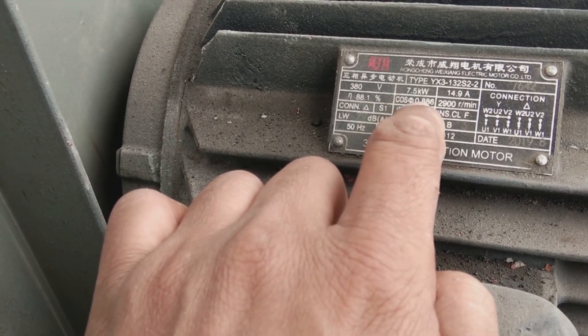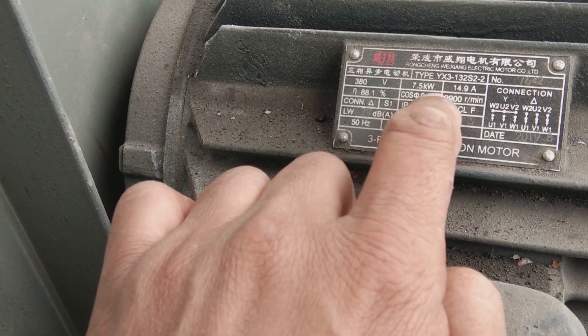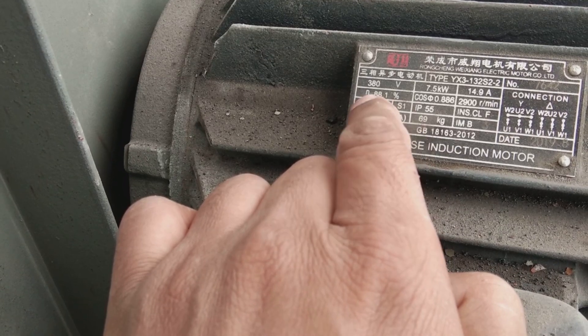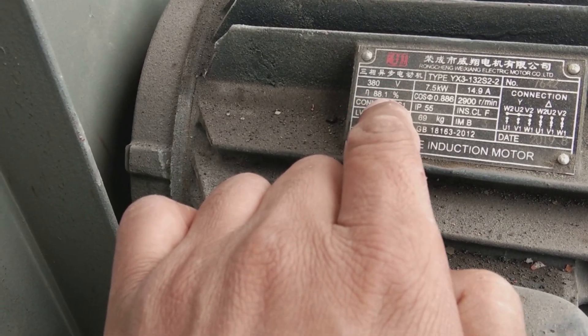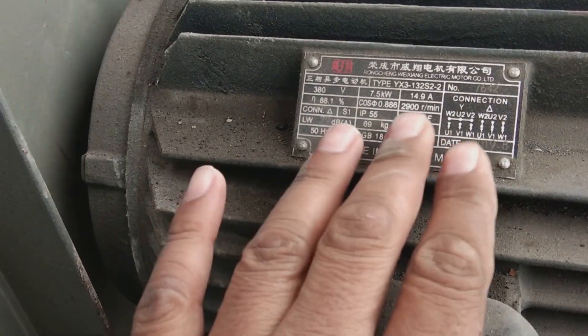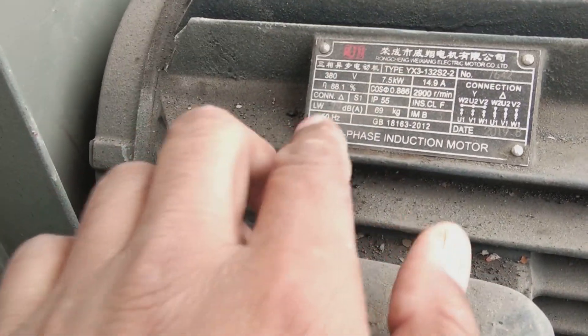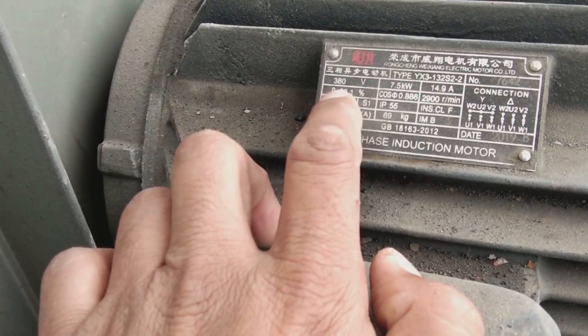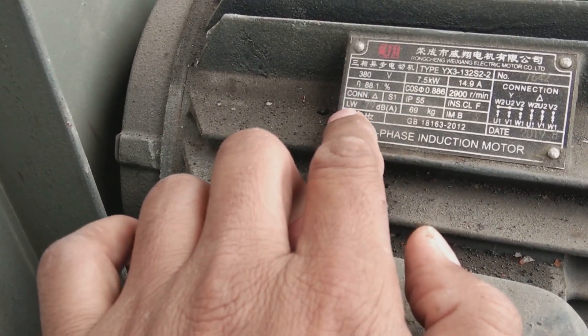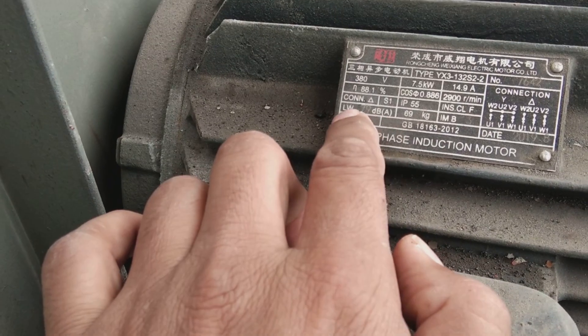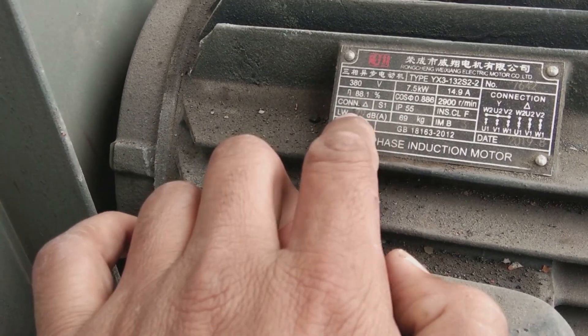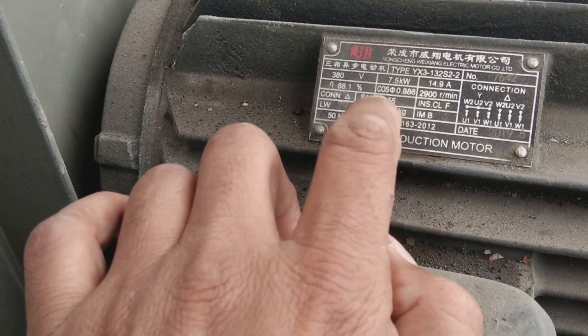Efficiency is 88.1%, which is not very good for such a motor. If it were above 90%, it would be considered good, but this is acceptable. The noise level while running is 79 decibels, as written here.